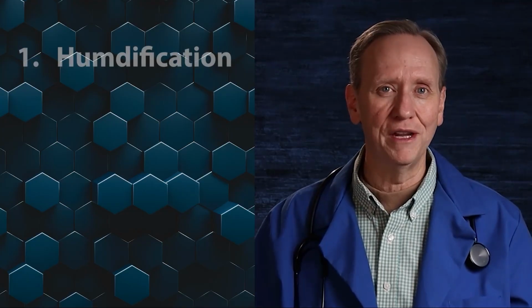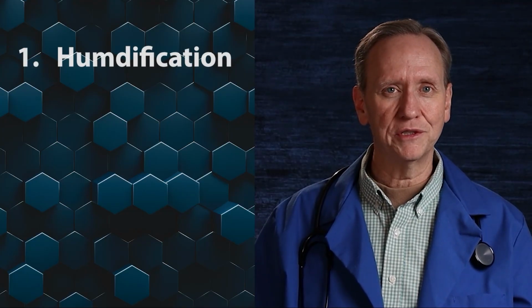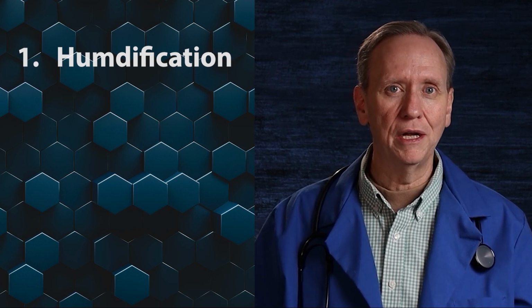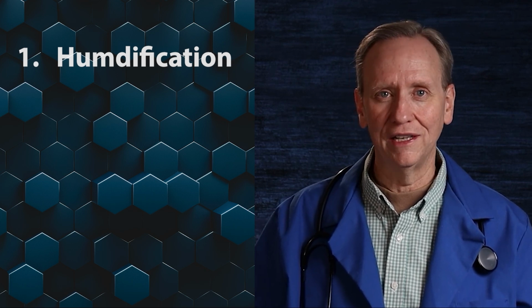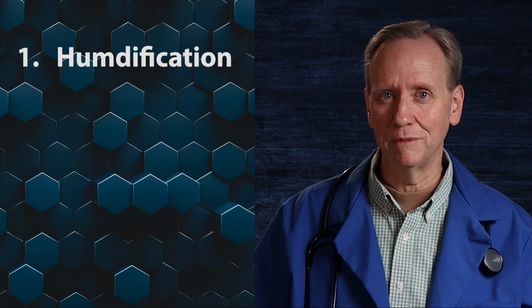Well, and specifically a high-flow nasal cannula, if you think about this, if you're going to be taking oxygen and getting it inside the patient's nose at 10, 20, 30, 40, 50, 60 liters a minute, you have to realize that that's too much dry gas. That would cause tremendous drying out of the mucosal tissues and cause damage to the upper and certainly the lower airways. And so one of the main considerations here is that we also have to humidify it. That's why you'll hear it called sometimes not just a high-flow nasal cannula, but a high-flow heated humidified nasal cannula. Those words are sometimes interchangeable.